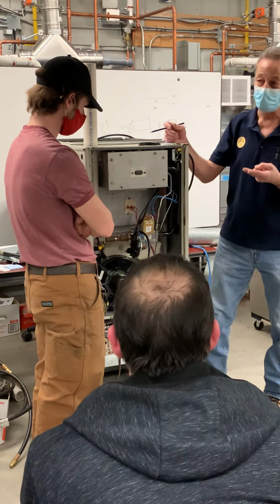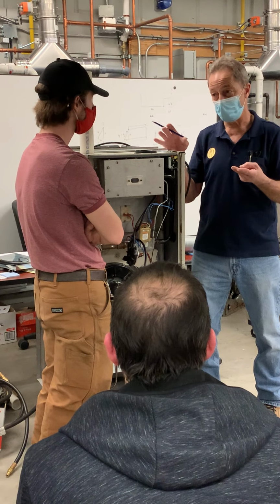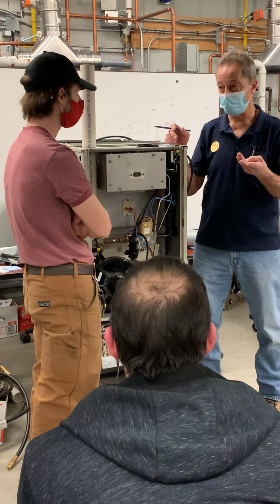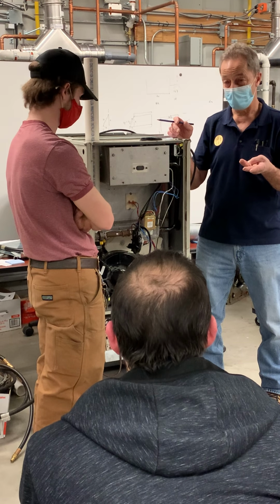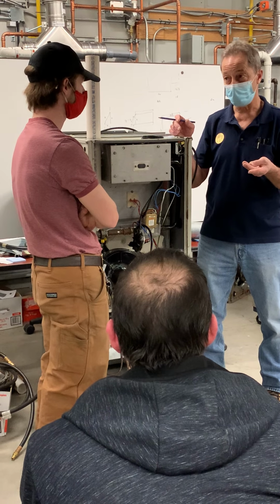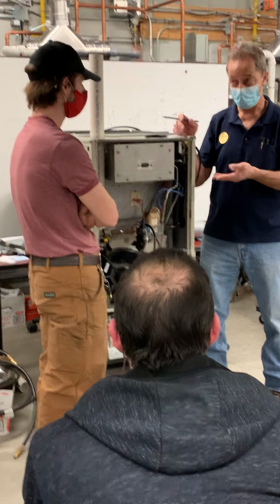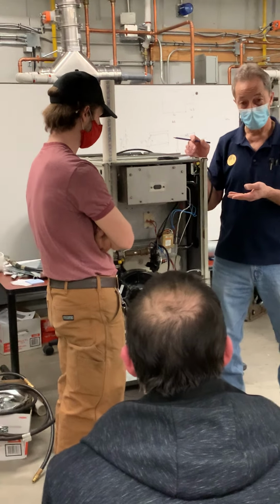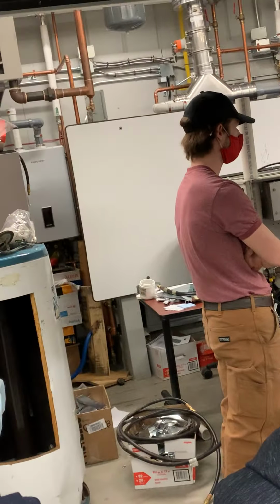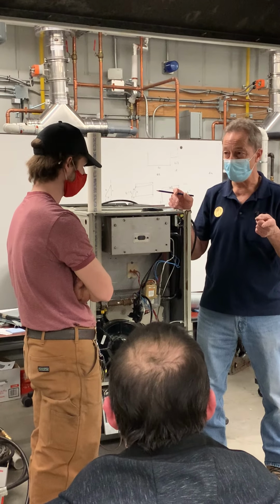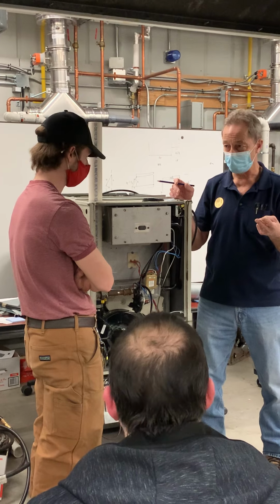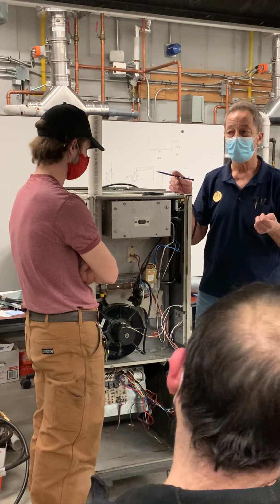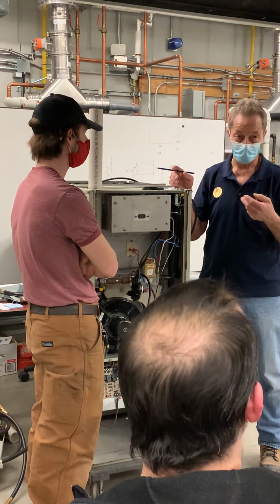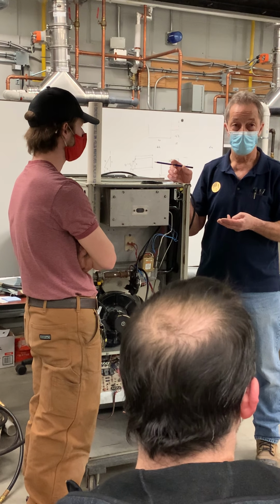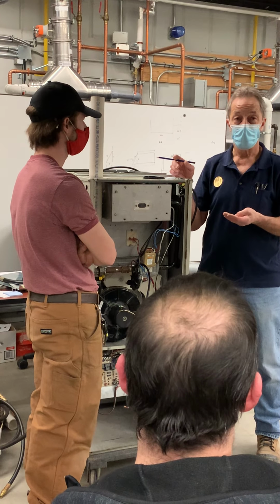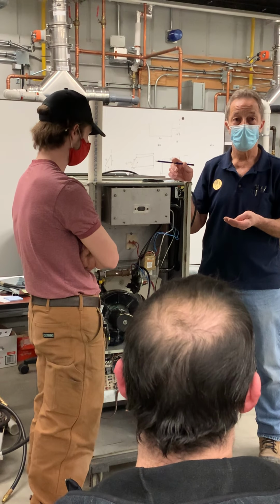What does it do next? I'll help you out a little bit. Energize 2 small coils, 2 small relays, yeah, 2 sets of contacts closed. What do those 2 contacts do? Probably the HSI and the pilot valve. Thank you. So HSI gets energized, pilot valve opens. What happens next? The HSI will heat up and then light the pilot, correct? And then the flame will be sensed, correct? And then that'll open up the main.